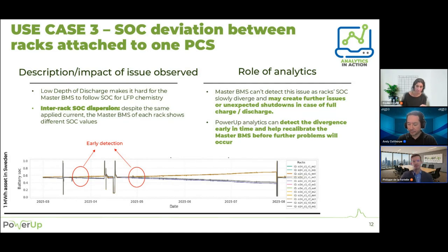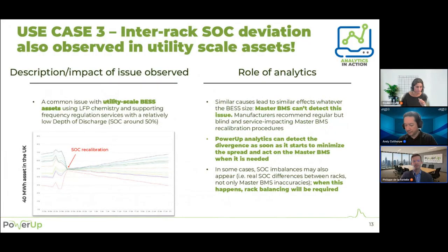Absolutely, Elodie. And I think the impact in such a case, where you have all the racks potentially connected to the same PCS leading to a shutdown, is much larger, right? It can be a large number of racks connected to a single PCS, and if all of those are affected, the energy affected is much larger than when we're looking at the same phenomenon within a single rack. Here we're talking tens of racks, potentially all affected, placing all the others at a lower capacity figure.